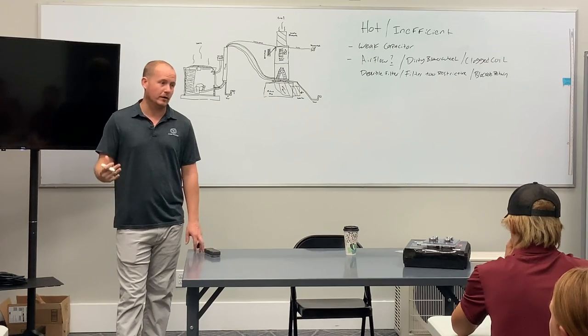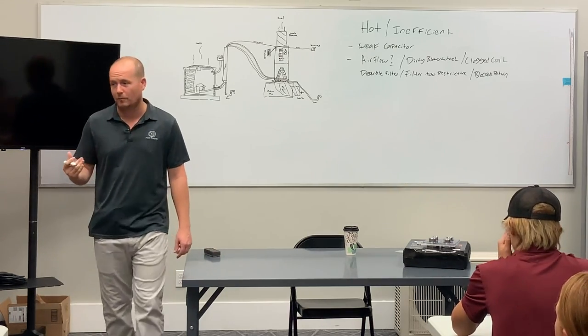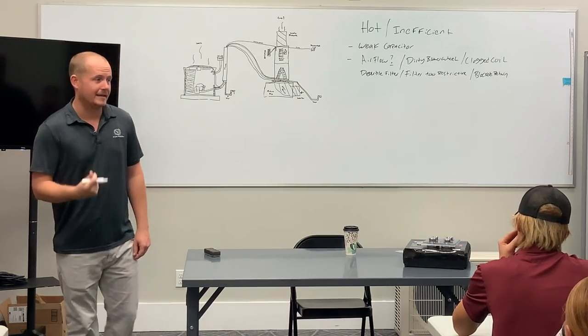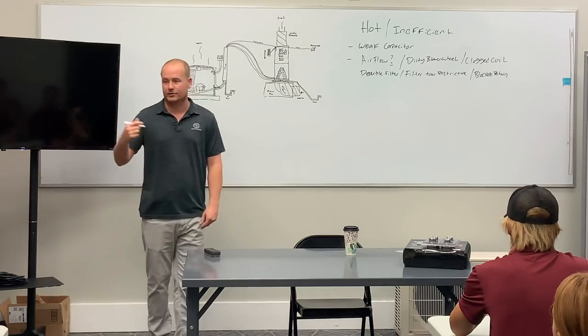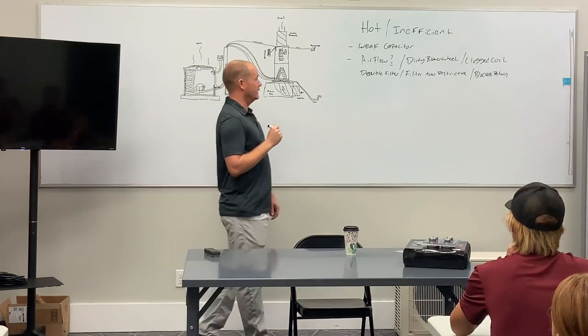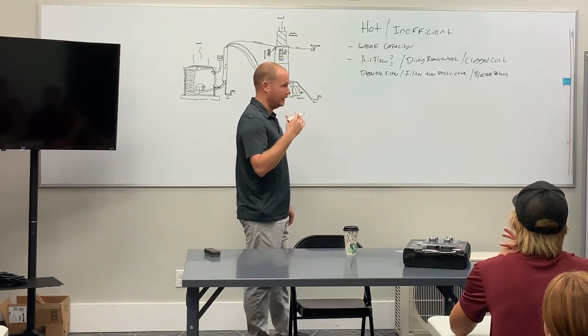When you restrict that coil, it is going to run inefficient. So from a practical standpoint, low airflow equals bad, either way. But one of the reasons it equals bad is not just that low airflow impacts the refrigerant side of the circuit, impacts your suction pressure, all that. It also impacts your motor temperature and efficiency in most cases, other than a PSC blower motor.